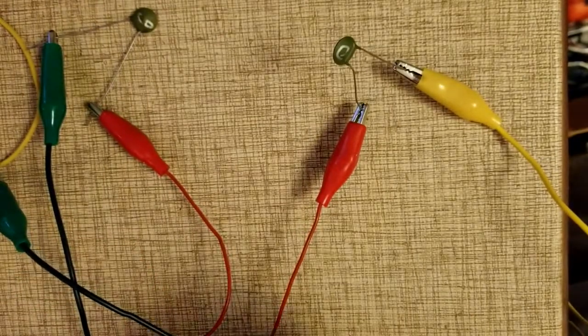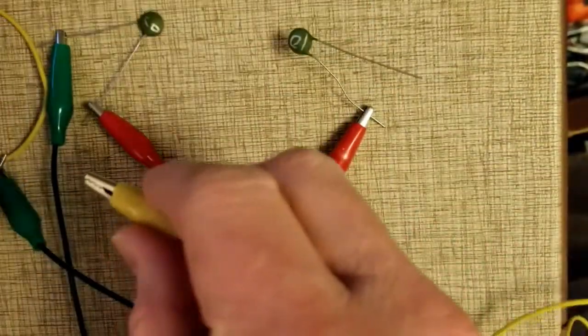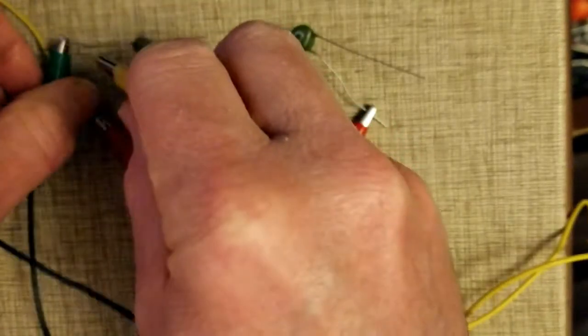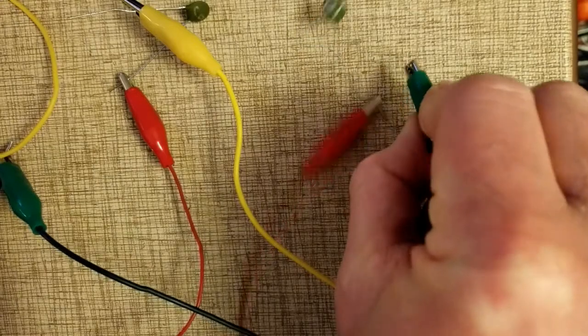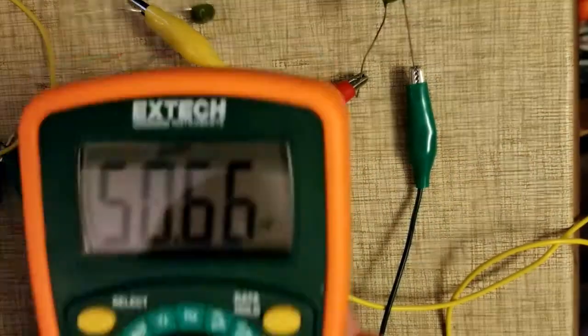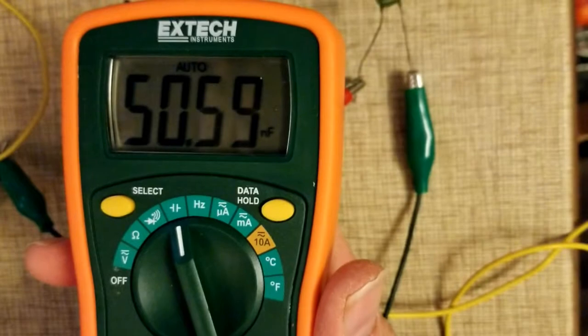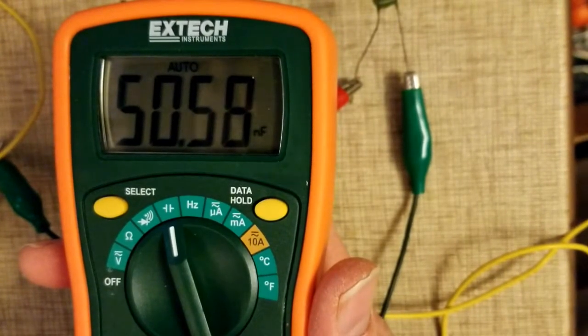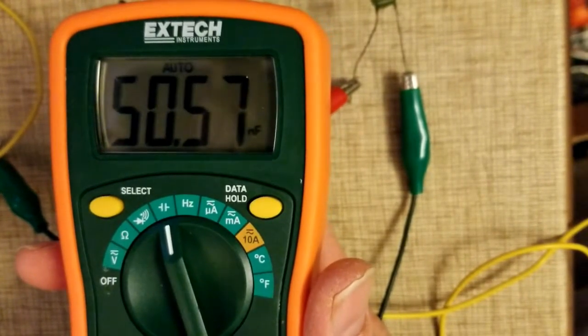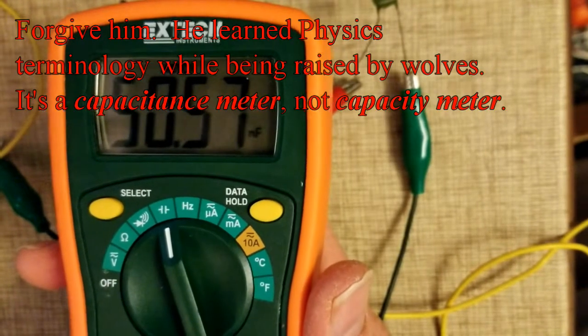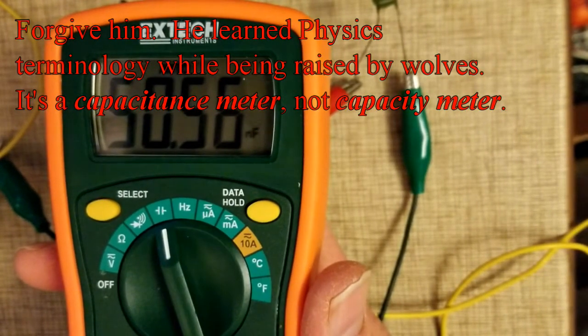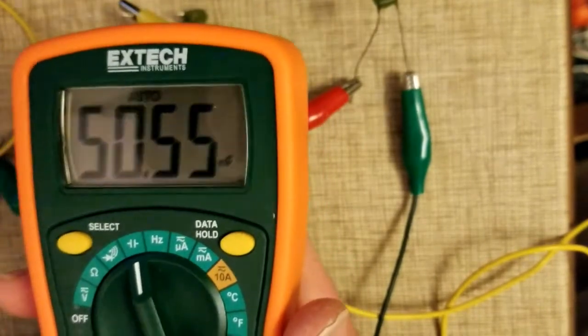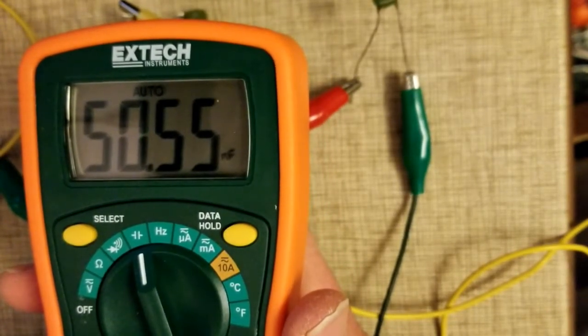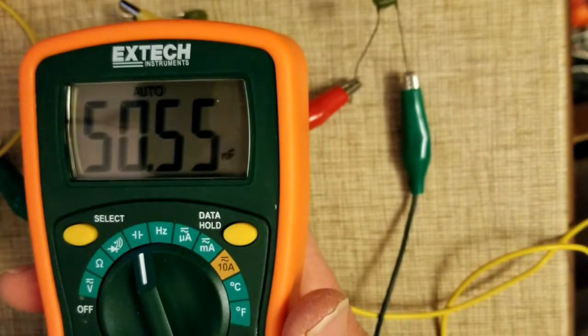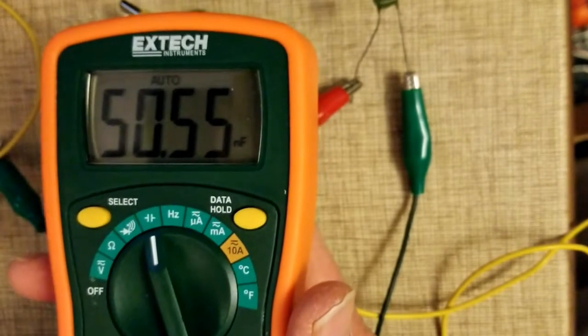Notice if I switch the lead, so basically going to put the high side where the low side was for the probe. So connecting yellow over there and going to connect green over here. And you get pretty much the same thing, if not the exact same thing. So there's no negative that pops up because the capacitance meter doesn't really care about the high side or low side. All right, please go with the first value when I had it hooked up. Pick one. You got two answers there. Pick one.